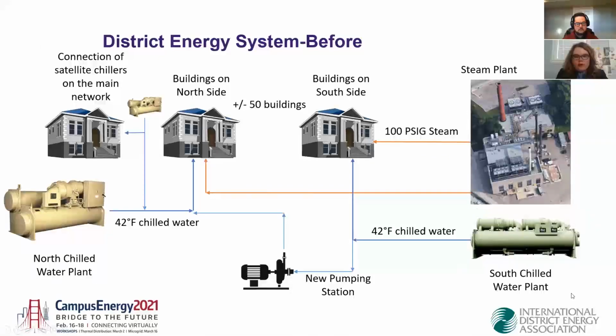So we have here this South Chilled water plant, the North Chilled water plant, and we have here that new pumping station that allows us to either pump water from the south to the north or vice versa, from the north to the south. And again, we still have our 100 PSIG steam that's going to every building, but we're using that network as an energy network that connects every building together. And we're adding in buildings some satellite chillers or some heat pumps that will recover the energy in that chilled water loop to heat every building. So basically we're sending energy in that chilled water loop to avoid replacing the steam plant. Over time, it's going to save capital costs because we're reducing load in every building. And when every building has been done, then we're going to figure out what we do with the steam plant.